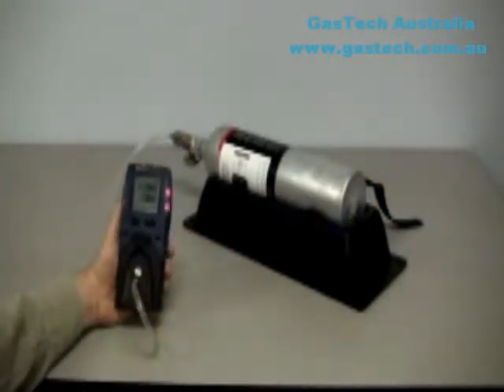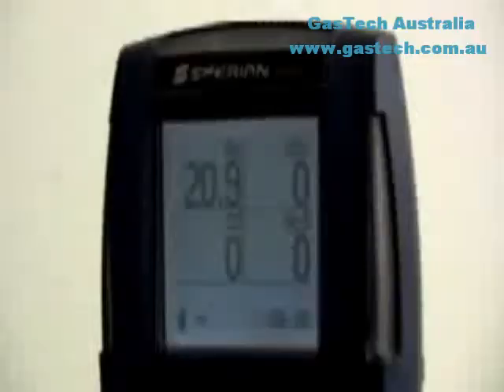The alarm should activate. If the LEL and toxic gas readings fall between 90% and 120% of the concentrations printed on the label of the calibration gas cylinder, then the readings are considered accurate, and it is safe to use the instrument without further adjustment. If the readings do not fall within the 90% to 120% window, then the detector is considered inaccurate and must be span calibrated before further use.